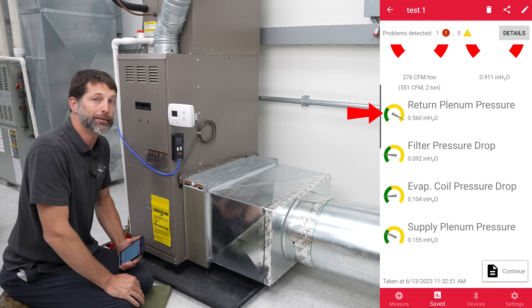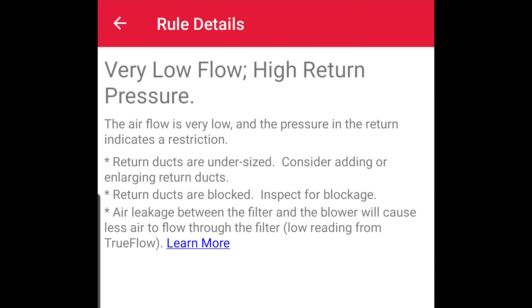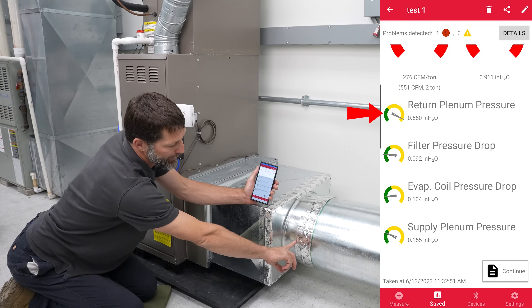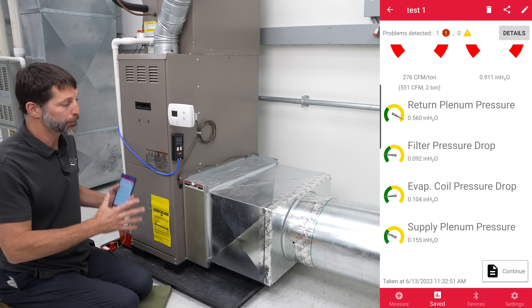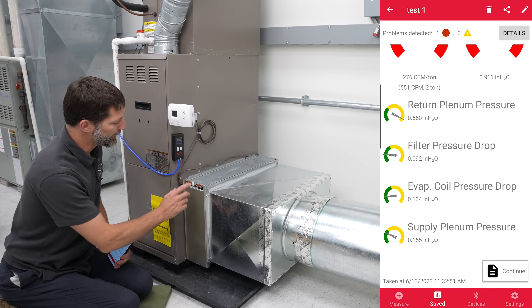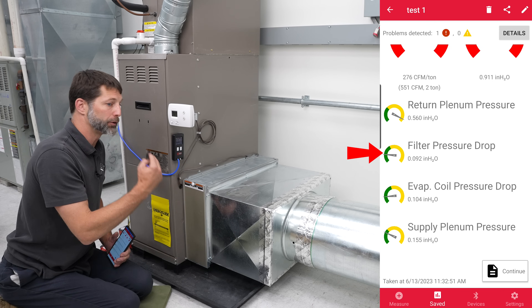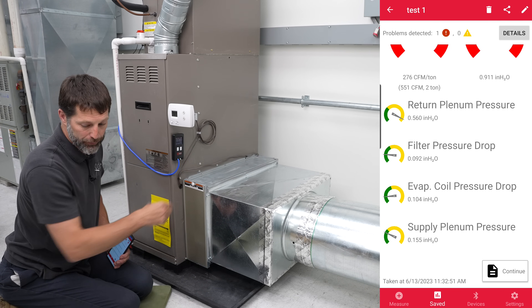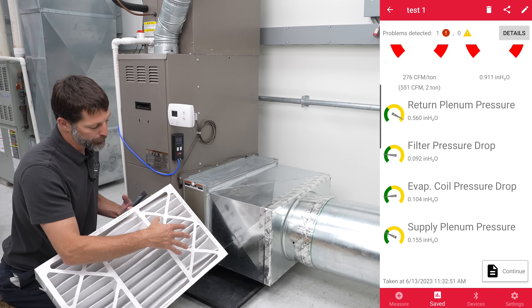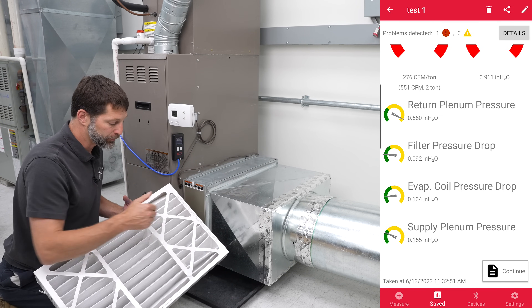Our problem is that we have high static pressure in the return plenum, and that means we have a restricted duct — meaning it's too small, something is closed off, or maybe the duct has collapsed on itself, like a flex duct that's collapsed. That's where the problem is. Wherever you have high static pressure, the problem is going to be upstream of that measurement point. Static pressure is the pressure applied by the blower motor in order to move the airflow through the ductwork. High static pressure is always an indication of a problem at that spot. If we had high static pressure across the filter, we would know the filter is clogged or too restrictive. A pleated filter like this increases surface area for the air to pass through, reducing static pressure while still collecting debris.